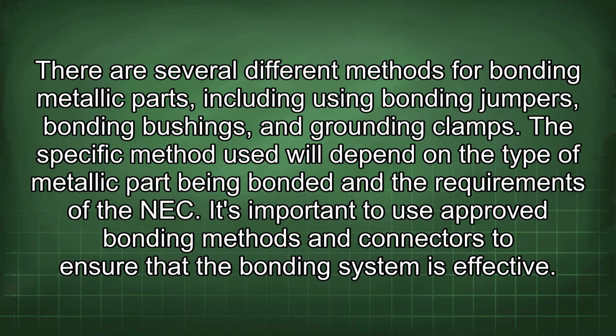There are several different methods for bonding metallic parts, including using bonding jumpers, bonding bushings, and grounding clamps. The specific method used will depend on the type of metallic part being bonded and the requirements of the NEC. It's important to use approved bonding methods and connectors to ensure that the bonding system is effective.